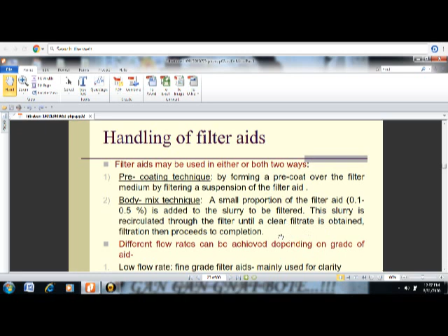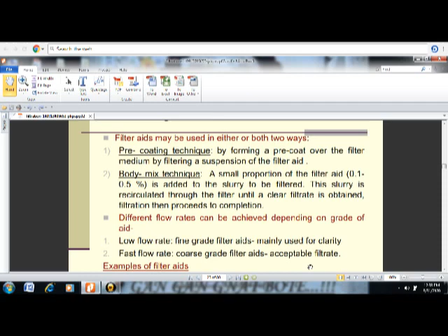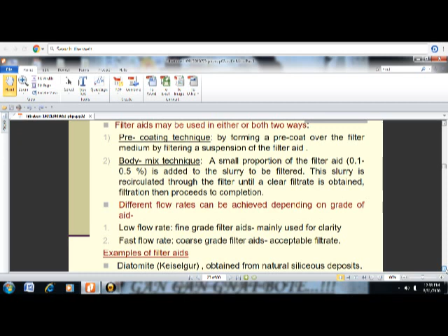Now different flow rates you can achieve by using this. You can go for the low flow rate also, and you can go for the fast flow rate also. Generally if you need very good clarity, then go for the low flow rate. If you need an acceptable filtrate, then you can go for the fast. Generally if coarse grade filter aids are used, you get a fast flow rate. If they are fine grade, very fine, then it takes time for the solution to come out through the fine filter aid, but the clarity is higher compared to the coarse filter aids.